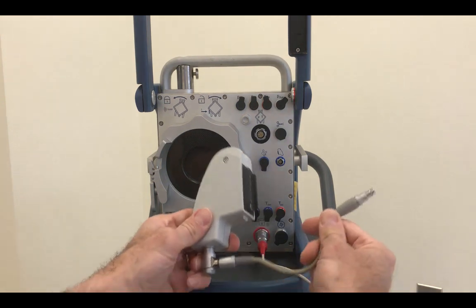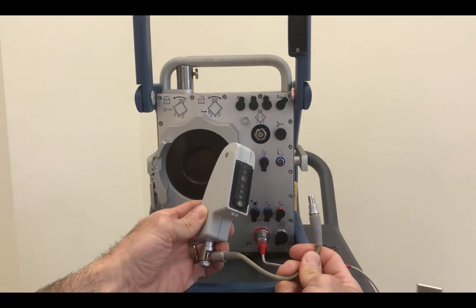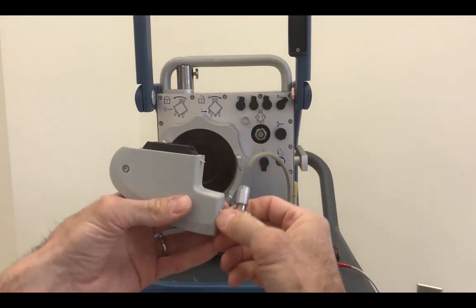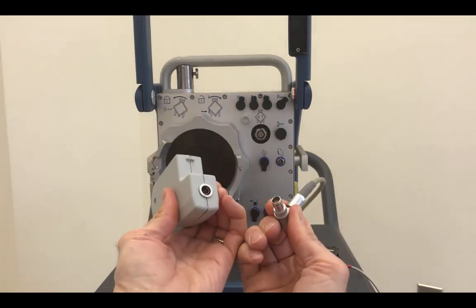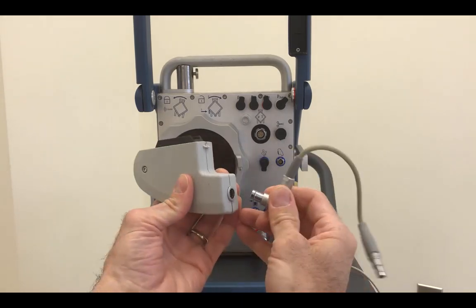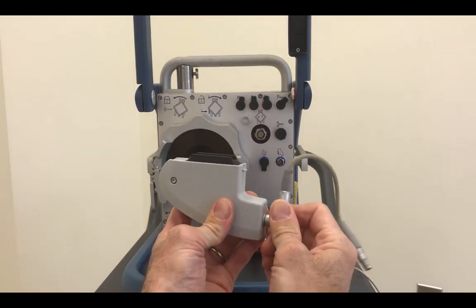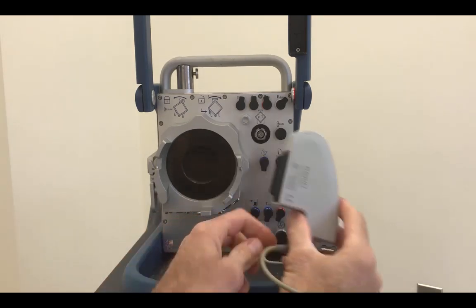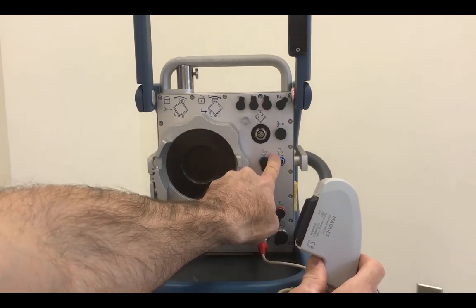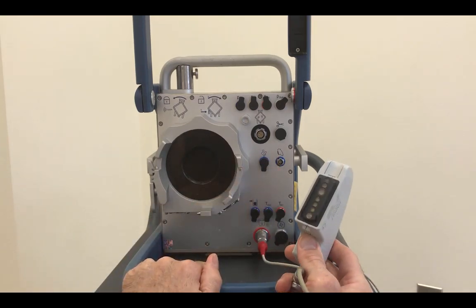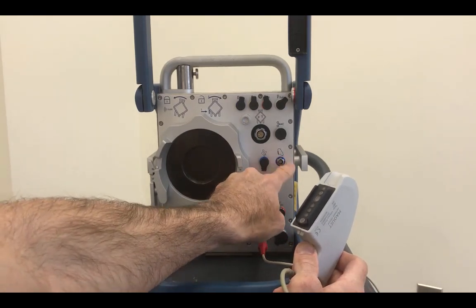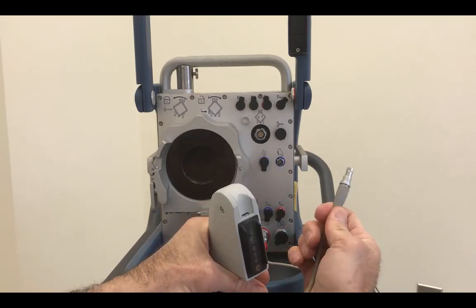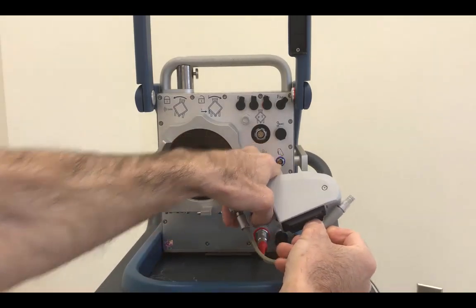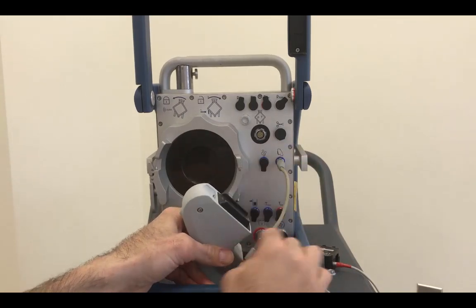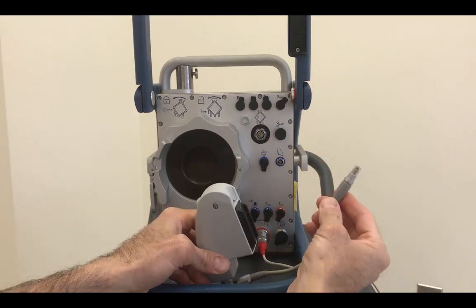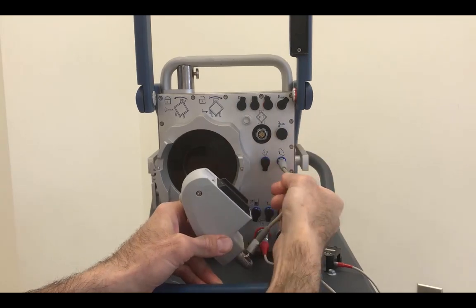Another connection you will almost definitely use is the SVO2 monitor. This is actually two pieces. These two pieces here come apart. The SVO2 monitor has this shape. There's a shape of module right there. The SVO2 monitor goes on the blue side of the circuit, on the venous line, so there's a blue stripe around that. And again, we're going to look for a red dot, line it up with a red dot there, push it straight in. To remove it, grab the collar to pull it out. If you don't grab the collar, it's tight.